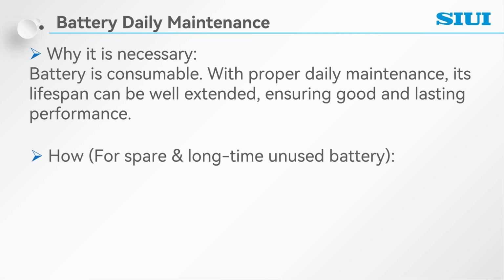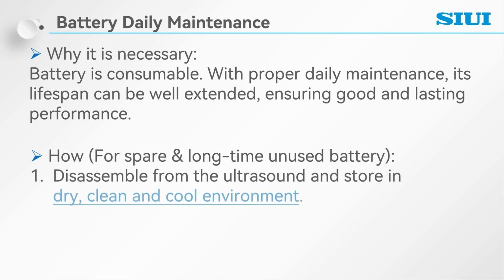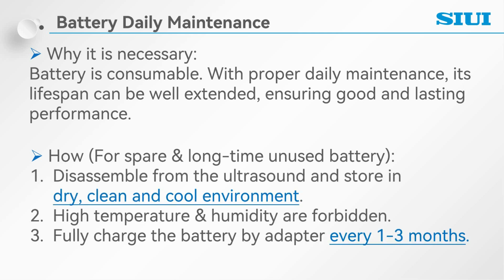For ultrasound systems that are used every day, the battery will be charged every time it turns on. While for spare batteries and long-time unused batteries, let's see SIUI recommendations as below. We suggest disassembling the spare and unused batteries from ultrasound systems and storing them in a dry, clean, and cool environment. Secondly, remember, high temperature and humidity are forbidden. And third, fully charge the batteries by adapter every 1 to 3 months.